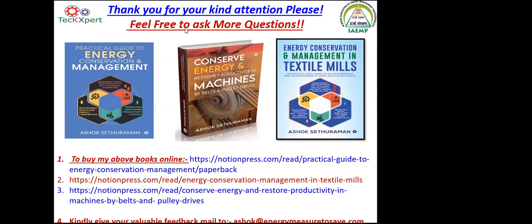This is from Mr. Shekhar. Request to explain the wet receiver and dry receiver once again, please. Thank you, Mr. Shekhar. The wet receiver is meant for, that is the post air cooler in the compressor hood that removes 70% of the moisture, and the air receiver that is next to the compressor is removing the moisture in the air at the ambient temperature. Once the moisture is removed, then only it has to go to the dryer. The wet receiver will reduce the load for the dryer, the refrigeration dryer, and the dry receiver will take care of the process demands of the cut in, cut out, or the flow measure. This one it will manage, whereas the wet receiver will try to remove the water in the air from the compressor to the dryer. That is the purpose.